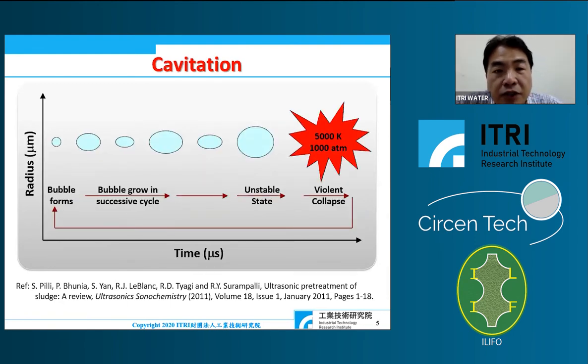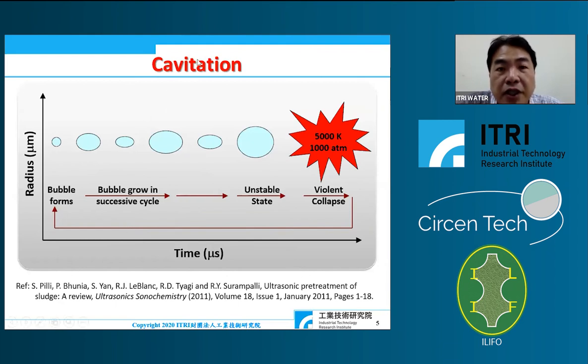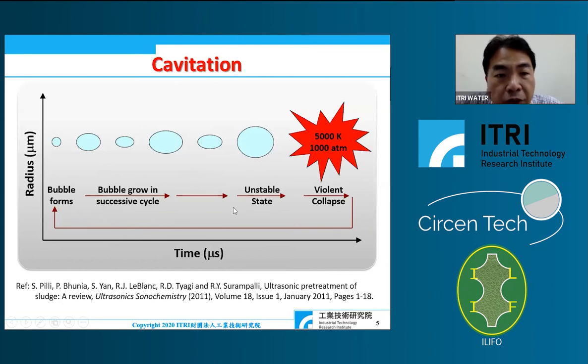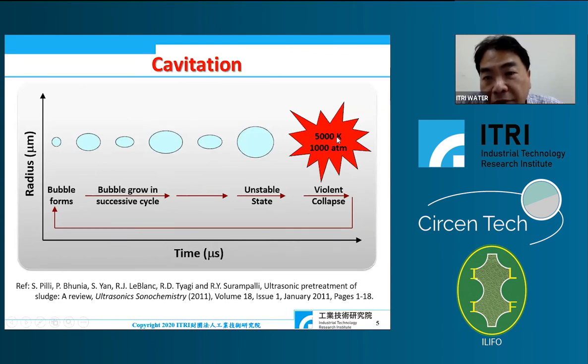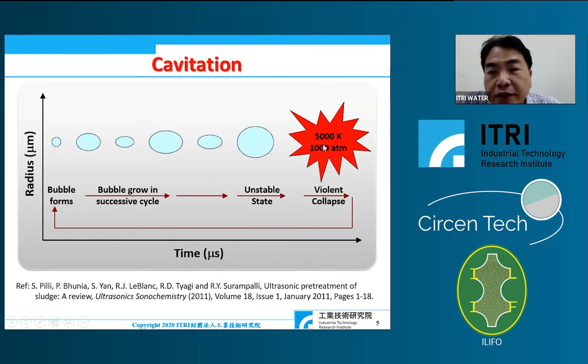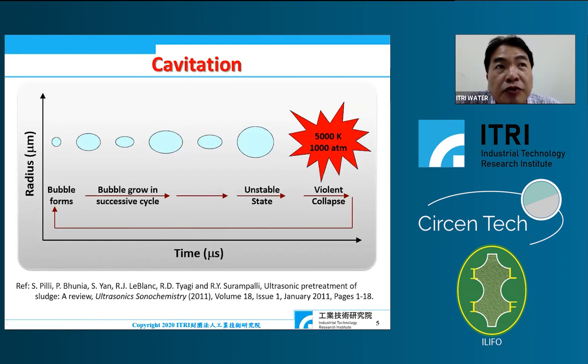The mechanism is cavitation: ultrasound generates bubbles in water, and when those bubbles collapse they create a hot spot — a very small area of extremely high temperature and pressure produced in a very short time. Sludge surrounding the bubble is struck by this high pressure, causing decomposition of the sludge structure. This is the desired effect for sludge hydrolysis.